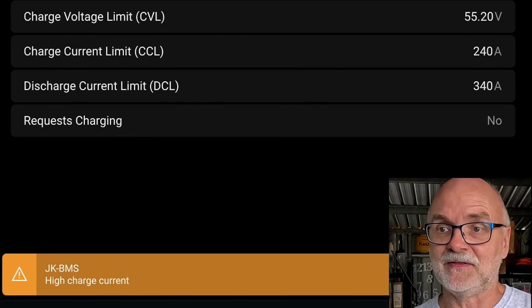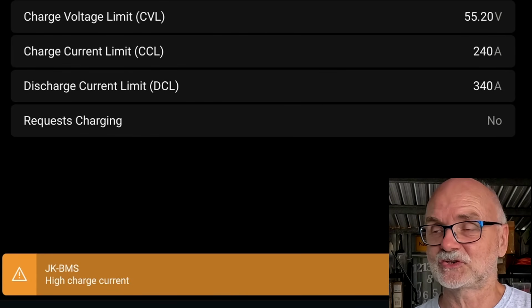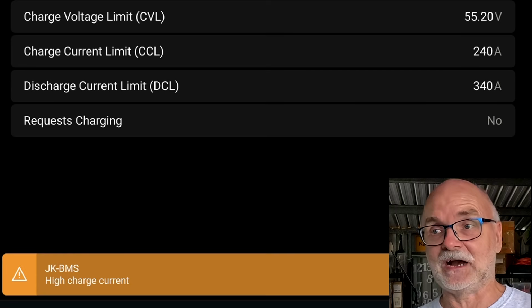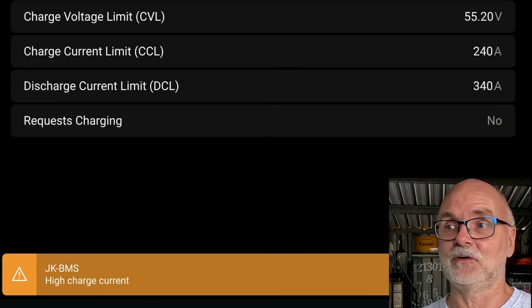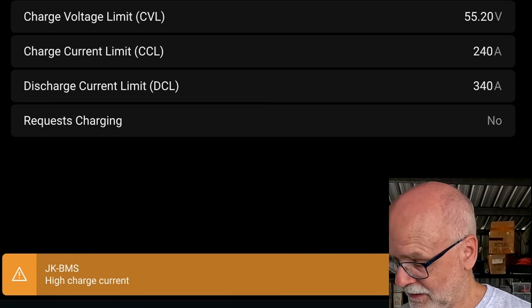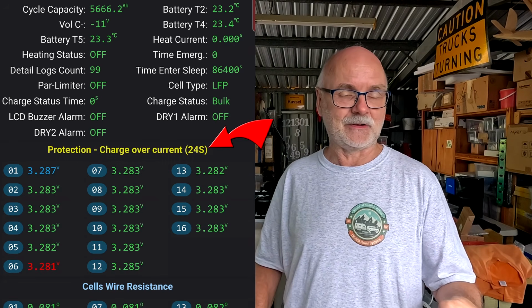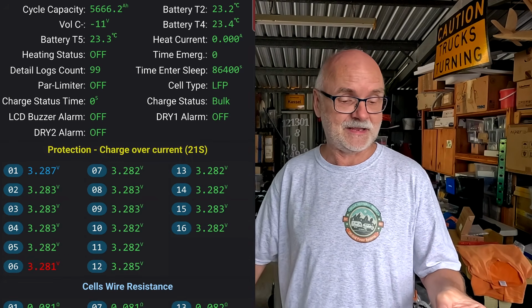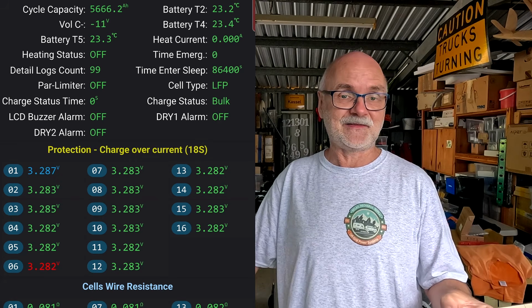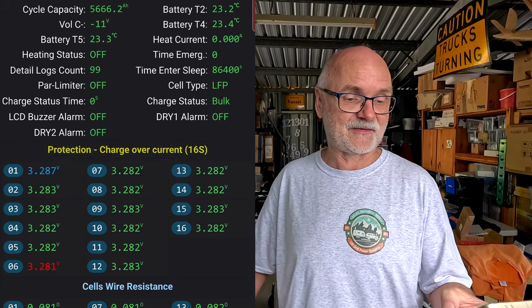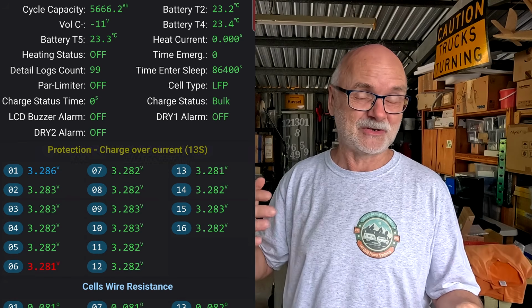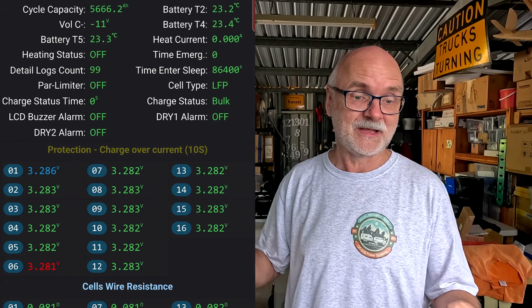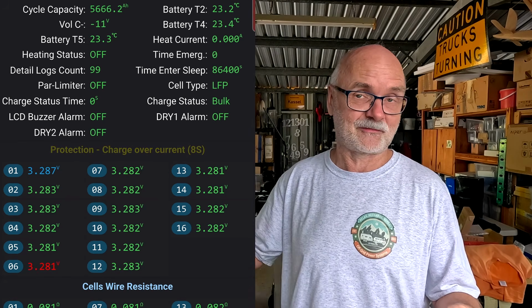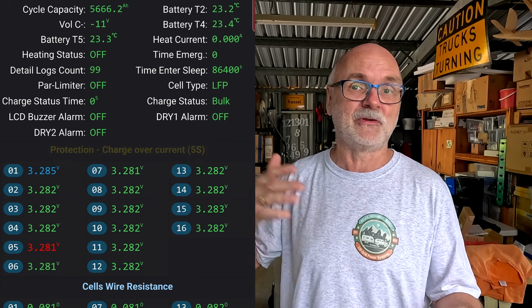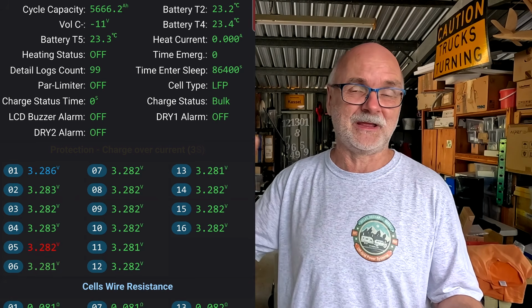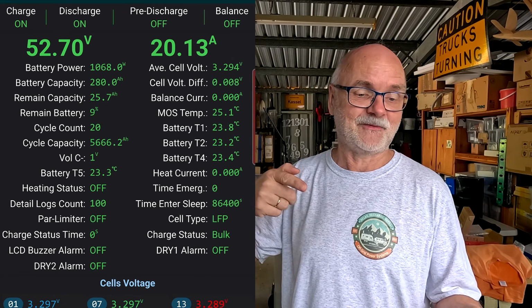And we have the same here in the inverter, JK-BMS high charge current. The CCL, the requested charge current, has reduced to 240 amps only. So that is all working perfectly fine. You can also see in the app here, there's a timer running now. Yeah, these are our 60 seconds we have set in the app. And in another 20 seconds, the BMS will turn off this alarm and try again how much current is actually coming into the battery. If it is still over 15 amps, our threshold we have set, it will go into alarm again. And it will continue doing this, yeah? Here we go. 20 amps going in.